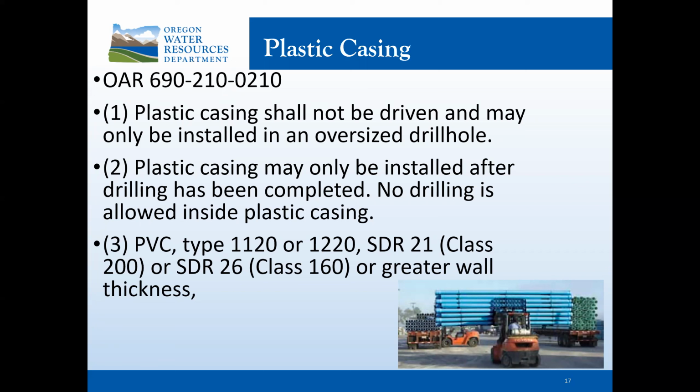Plastic casing may only be installed after drilling has been completed, and no drilling is allowed inside plastic casing. So again, that caveat right there, if a well has plastic casing, it can never be deepened or drilled out in any manner. So that's kind of the downfall of plastic casing, is that well can never be deepened.